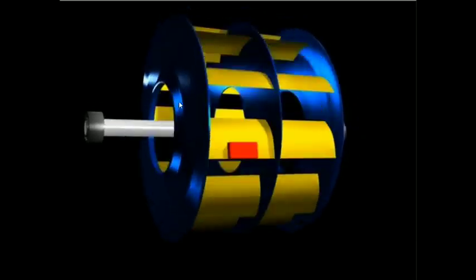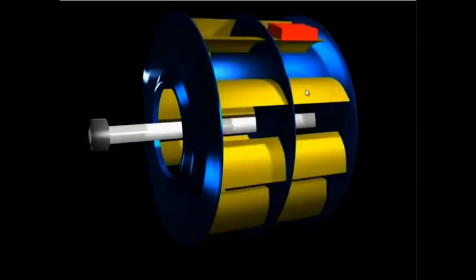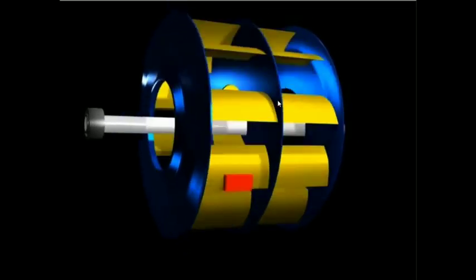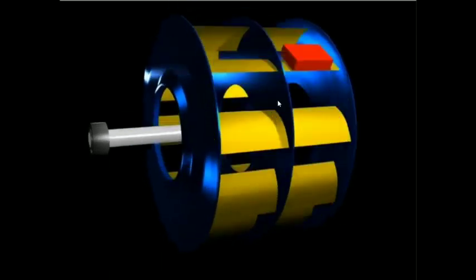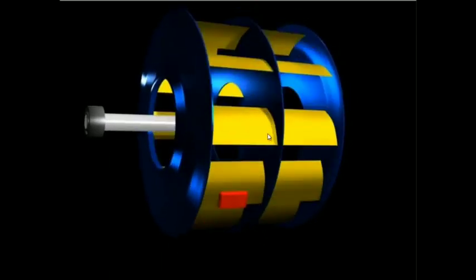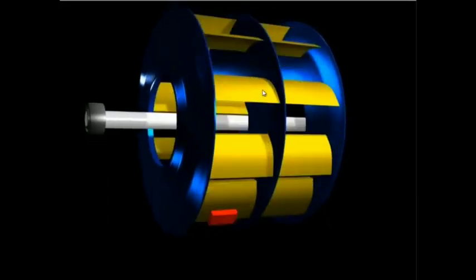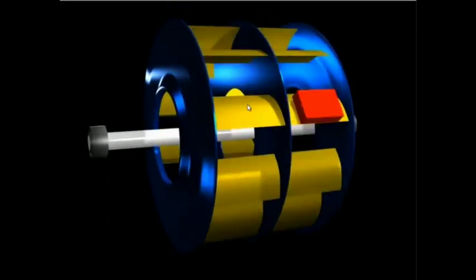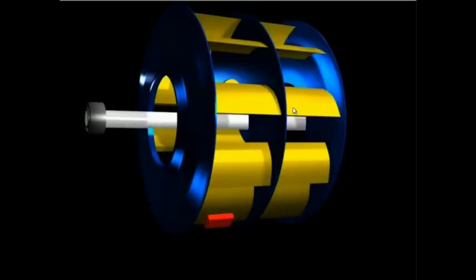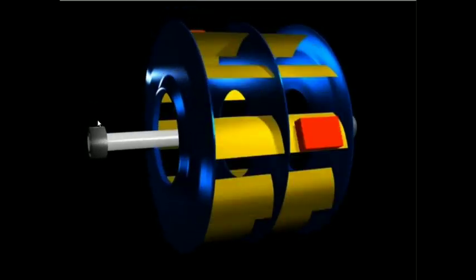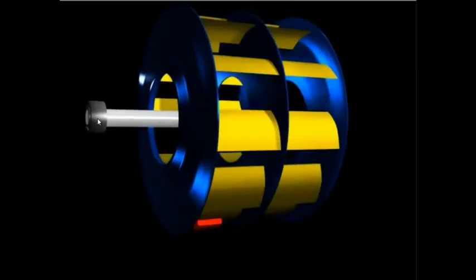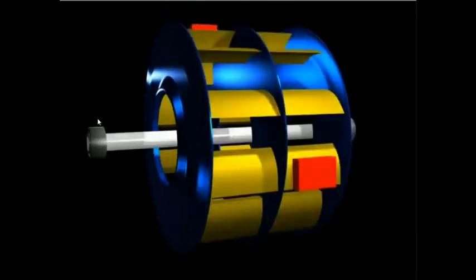If we have dynamic unbalance, the motion in this case may look a little more complicated, but in fact it's not. We have dynamic unbalance because it's a longer rotor and the distribution of the unbalance weight or erosion or corrosion, whatever is causing it, is not even. But it's still 1x vibration. There's no extra 2x or something like that.